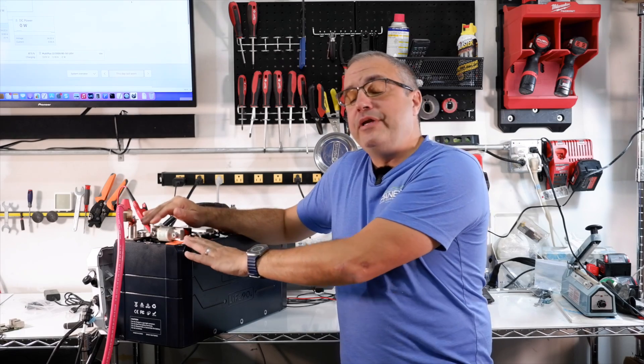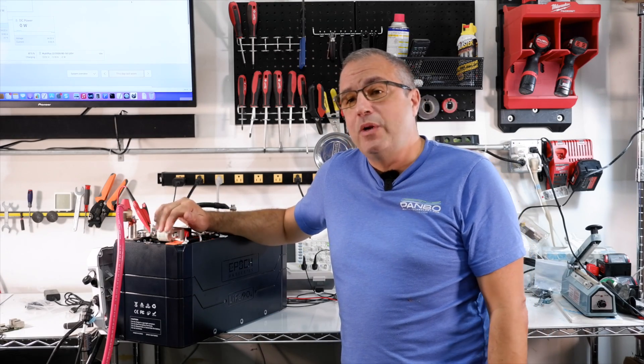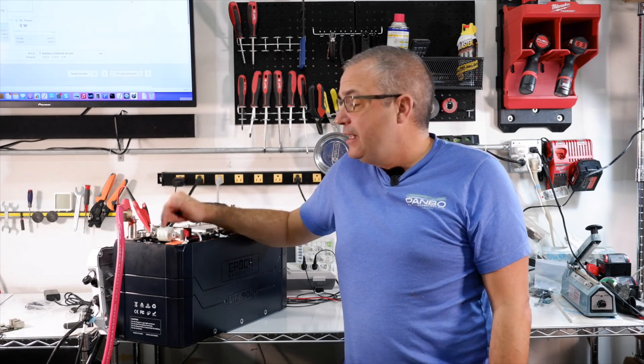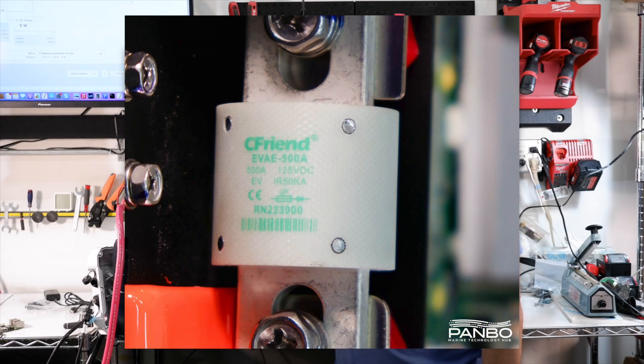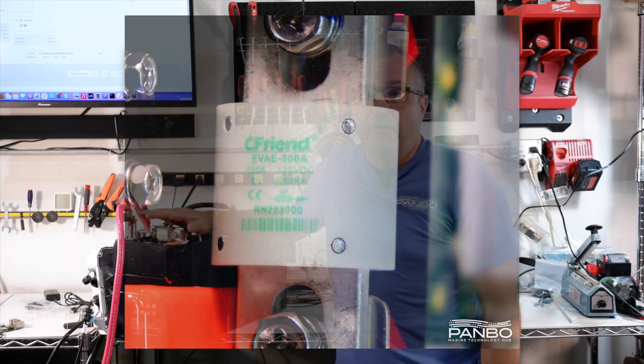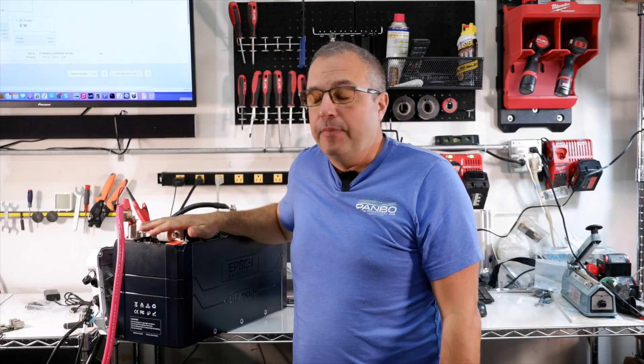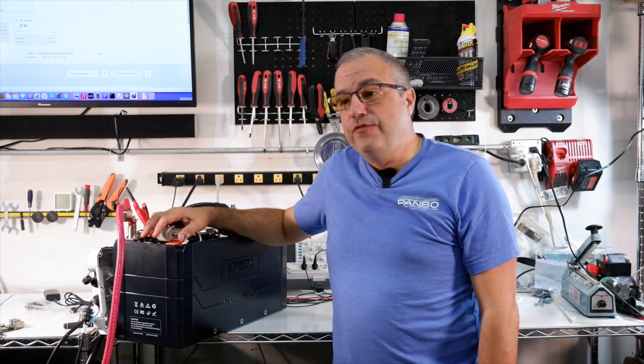Typical Marine Class T fuses are rated at 20,000 amp interrupt capability. This particular fuse is rated at 50,000 amps at 125 volts DC. That is basically the worst case scenario in terms of voltage as well as direct current for amp interrupt capability. So a very impressive fuse.